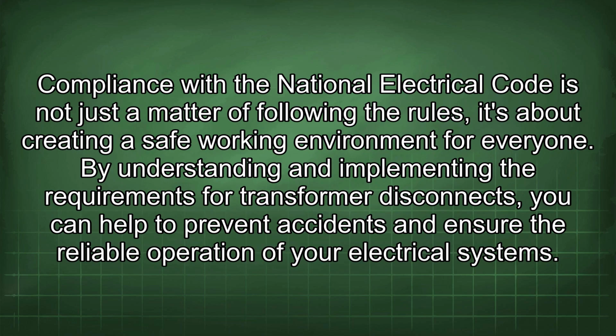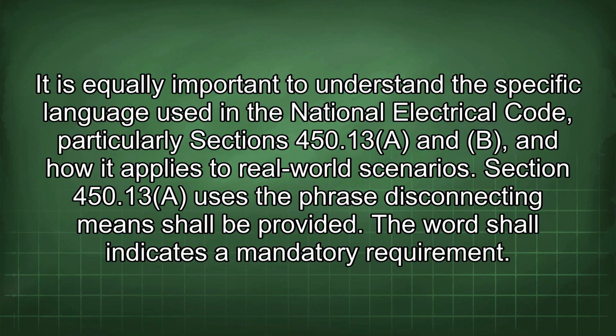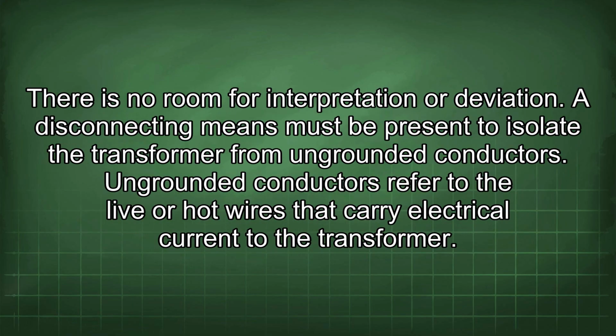Compliance with the National Electrical Code is not just a matter of following the rules, it's about creating a safe working environment for everyone. By understanding and implementing the requirements for transformer disconnects, you can help to prevent accidents and ensure the reliable operation of your electrical systems. It is equally important to understand the specific language used in the National Electrical Code, particularly sections 450.13 A and B, and how it applies to real-world scenarios. Section 450.13 A uses the phrase disconnecting means shall be provided. The word shall indicates a mandatory requirement. There is no room for interpretation or deviation.